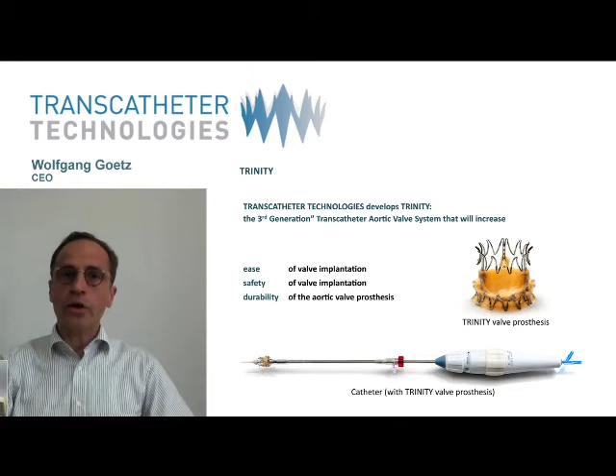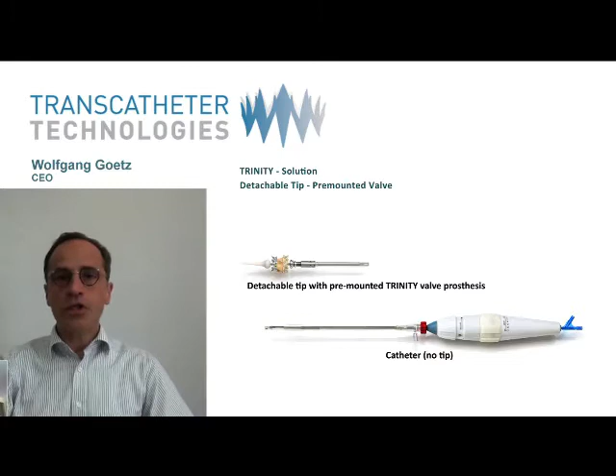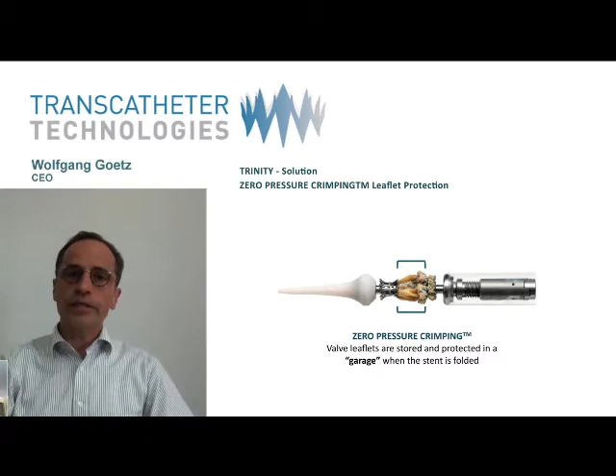The preparation for implantation is easier and faster because the valve is already pre-mounted on a detachable catheter tip that is just connected to the handle in the operating room before implantation. This will save expensive operation room time and will eliminate a technician who is needed to mount the valve right before implantation. The valve leaflets of Trinity are protected in a kind of garage when the valve is folded onto the catheter, preventing damage to the fragile leaflets. This is mandatory for increasing the durability of the valve prosthesis.